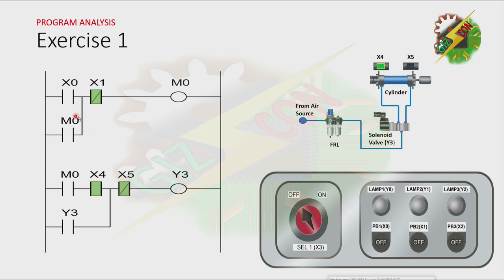M0 will not turn off because there is a latching here. Then the normally open contact of M0 will turn on. And because the cylinder is at fully retracted position, X4 will be energized. This will cause Y3 to turn on. And because there is a latching, Y3 will not turn off. The only way to turn off Y3 is by reaching the fully extended position, X5.